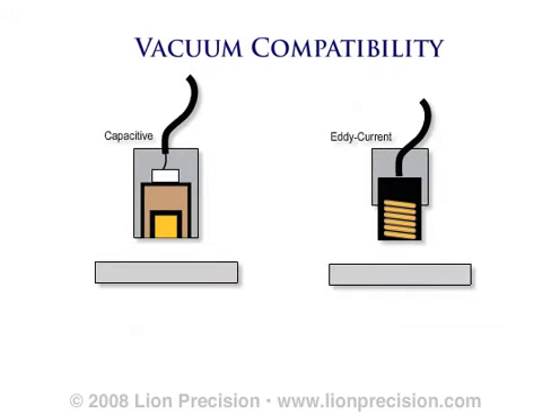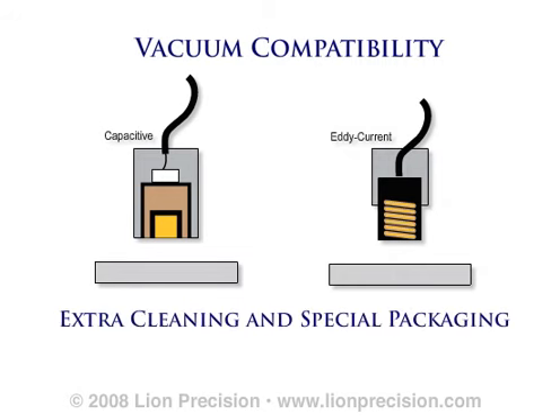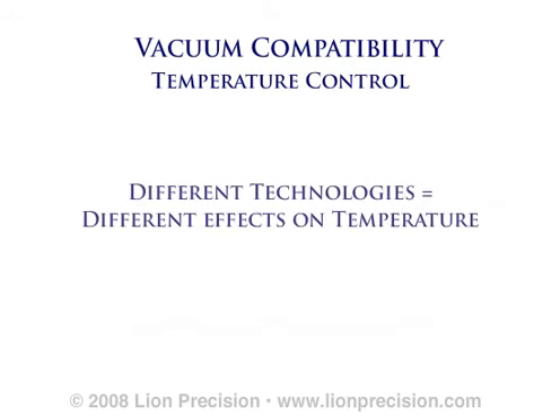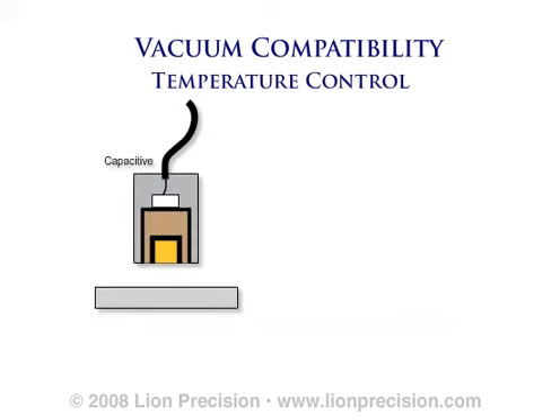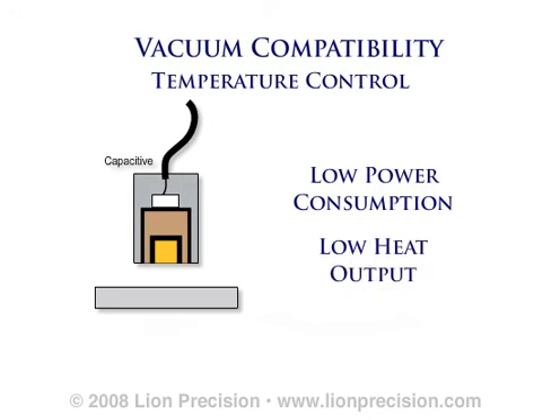Capacitive and eddy current probes can both be used in vacuum applications. Materials in the probes are selected for structural stability and minimized outgassing under vacuum. Vacuum-compatible probes are subjected to an extra cleaning stage and special packaging to remove foreign materials that may threaten a delicate vacuum environment. Many vacuum applications require precise temperature control. The probe's power consumption and its associated contribution to temperature change is where capacitive and eddy current technologies differ. A capacitive probe has extremely small current flow and power consumption. A typical capacitive probe consumes less than 40 microwatts of power, contributing very little heat to the vacuum chamber.